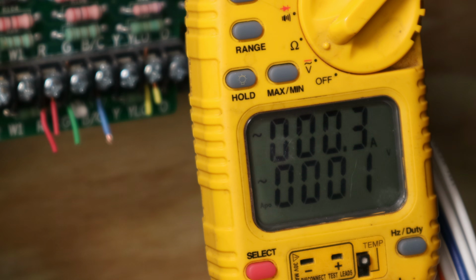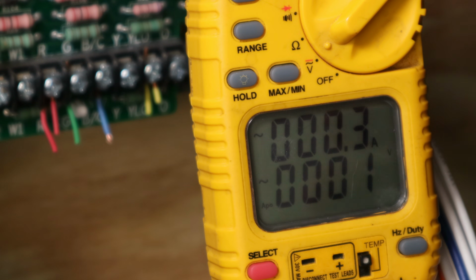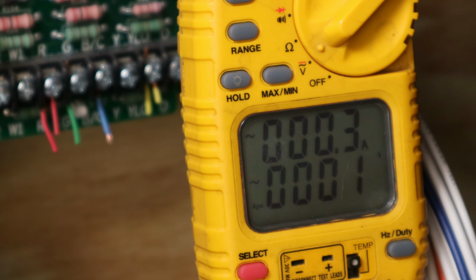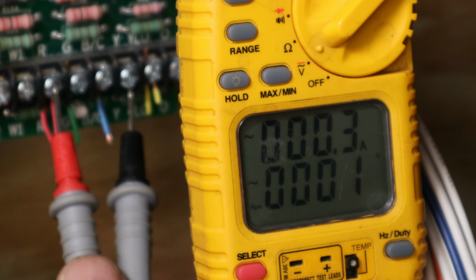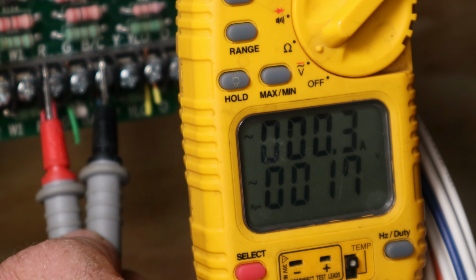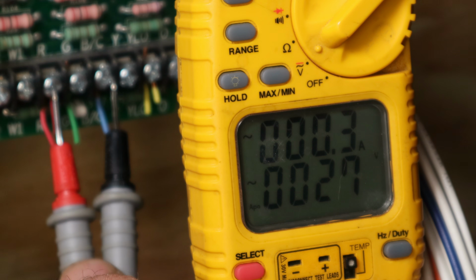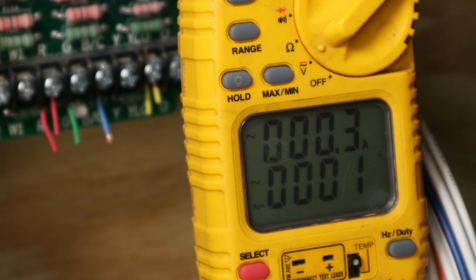Now, before I open up the ECM module and show you everything that's going on there, I'm just going to start with the troubleshooting process at this point because we're going to open up that module anyway. So one of the first things I'm going to do is check and make sure I actually have 24 volts on the system. To do that, real simple, just go between R and C on the control board terminals, and I'm reading about 29 volts there. So I know I'm getting low voltage to the control board, which means I should be getting low voltage through that diode bridge, the cap, the voltage regulator to the microprocessor.